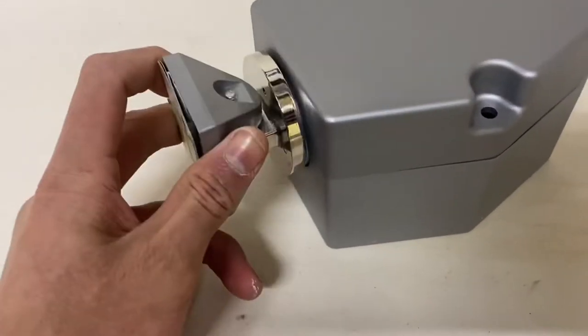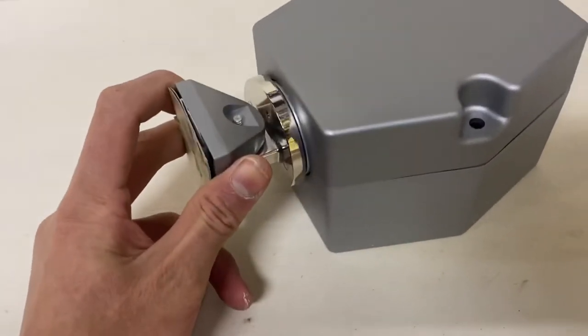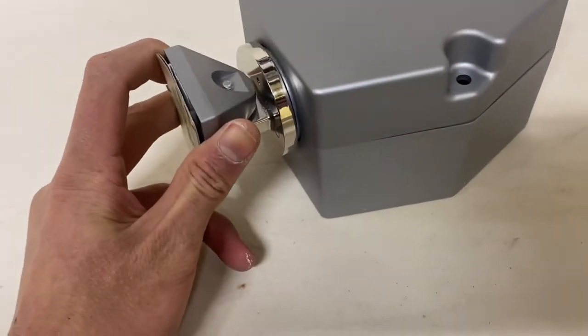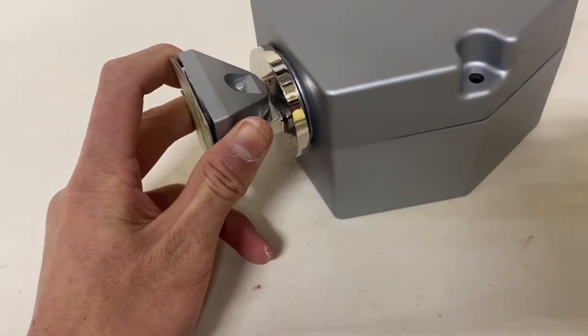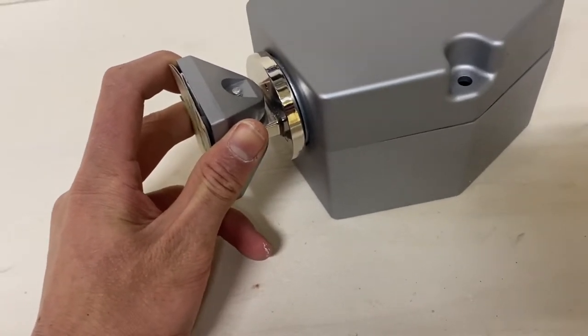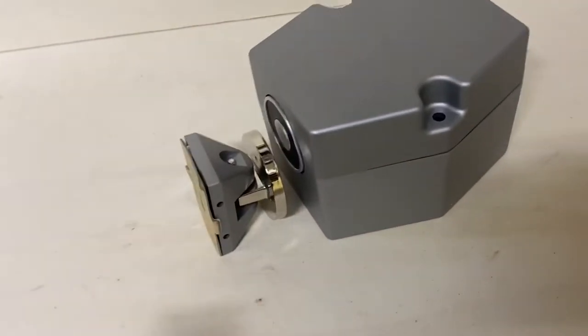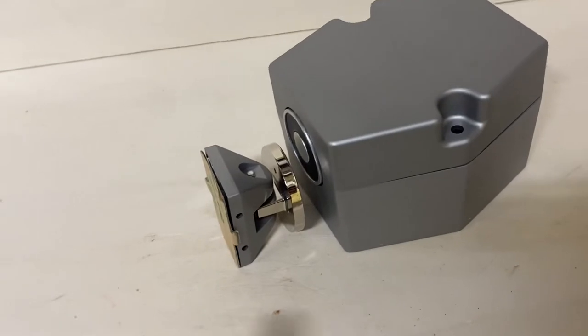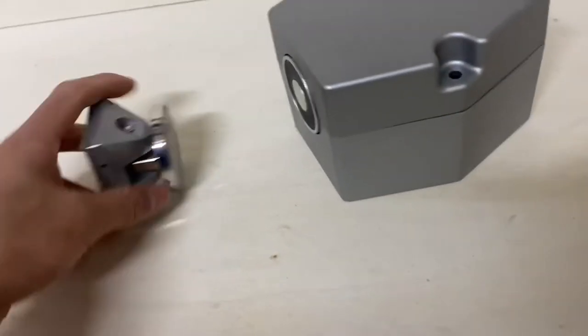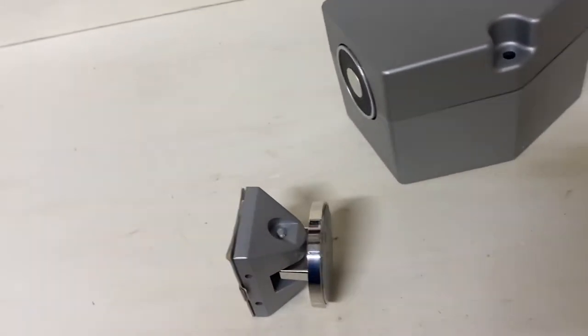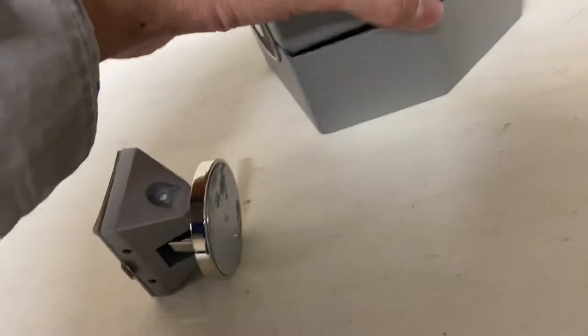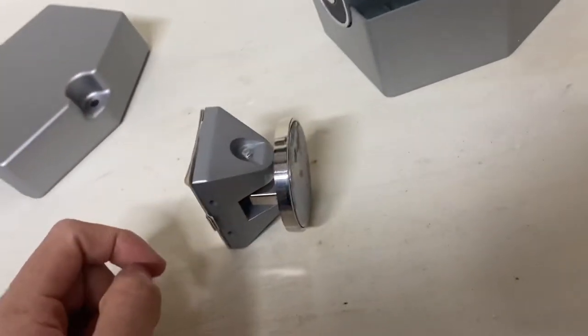So this part would be attached here because it's magnetized. And then when the fire alarm goes off, or the power going to this magnet is cut by the alarm panel, and then it drops the magnet, and then the fire door can then close because this part would be attached to the door. So yeah, now let's go ahead and wire it.